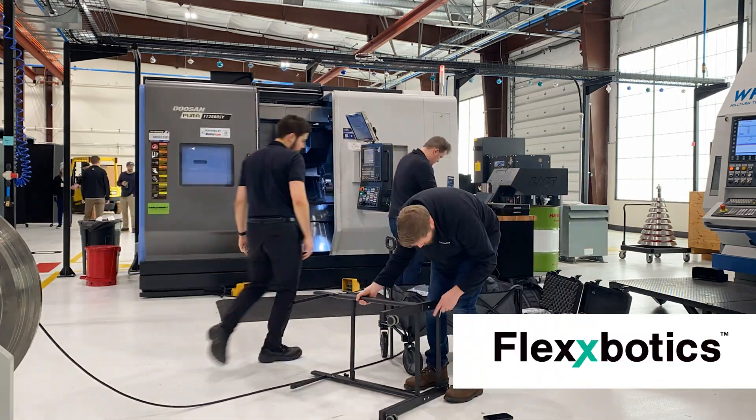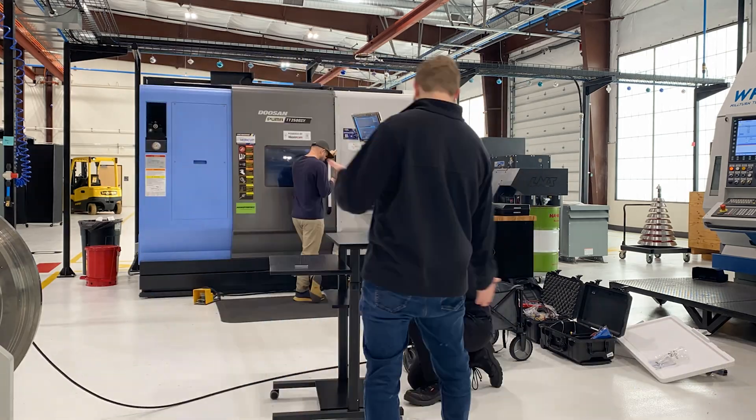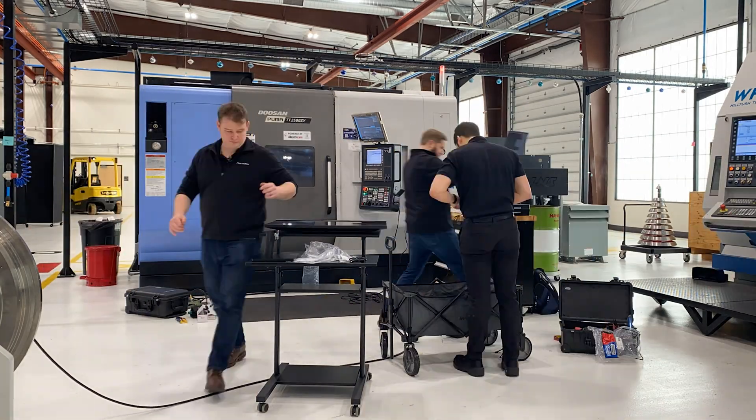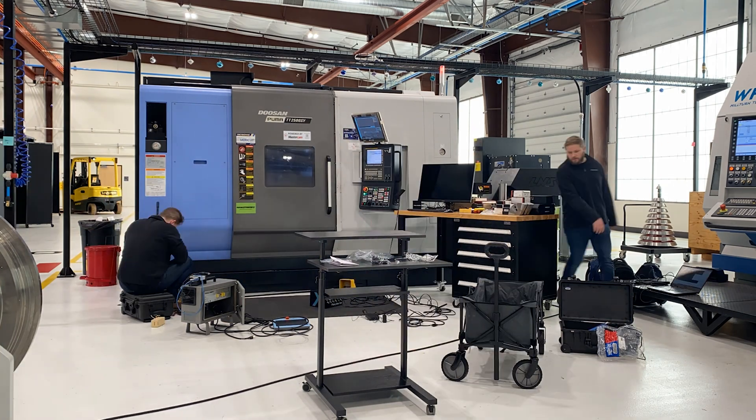We worked with Flexxbotics — they specialize in CNC robot integration, with specialty products and software. The biggest advantage was instead of having to tear open the back of the PLC cabinet, splice a bunch of wires, and have a giant umbilical coming out of the control cabinet, with a single Ethernet connection we were able to establish communication with all the I/O of the CNC and PLC.